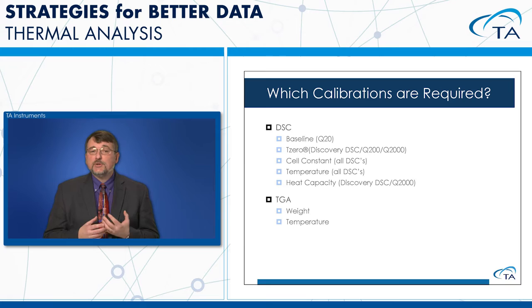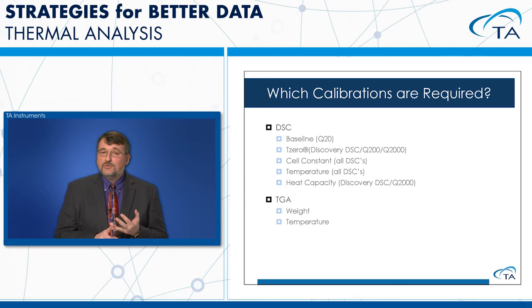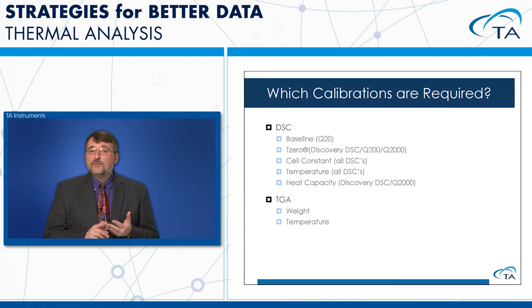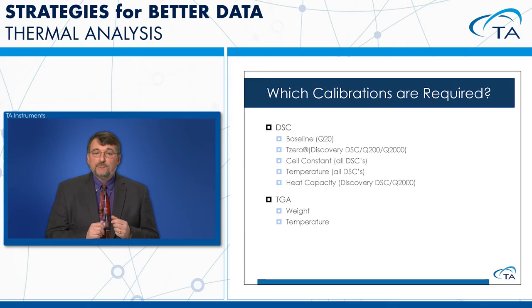The calibrations we do depend on which DSC you have. For the Q20 DSC, we have a baseline calibration. For T0 DSCs like the Q2000 and Discovery DSC, we have a T0 calibration. All DSCs have a cell constant calibration and a temperature calibration. The Q2000 and Discovery DSC also have a direct heat capacity calibration. For TGAs, we have weight calibration and temperature calibration.